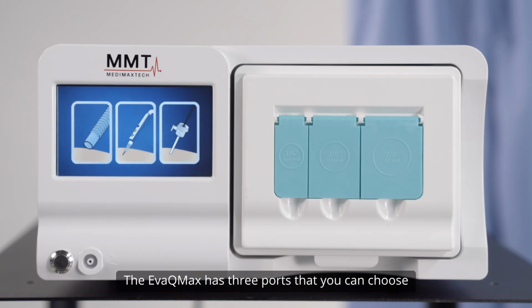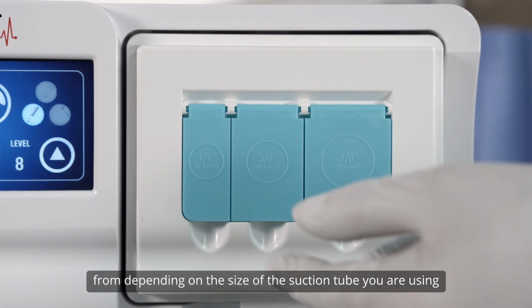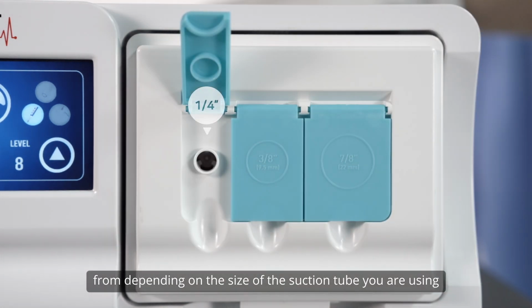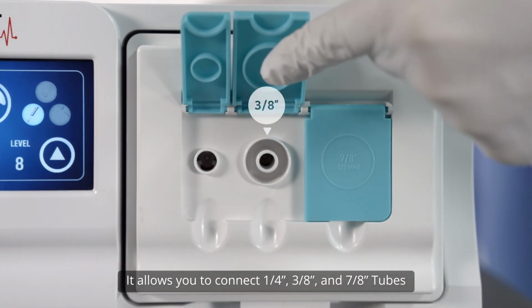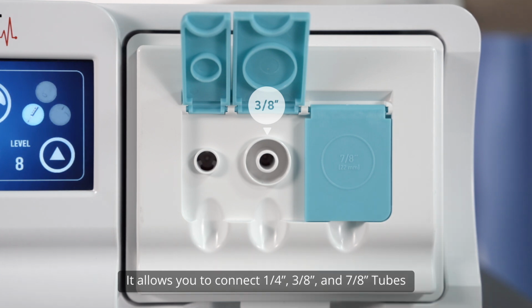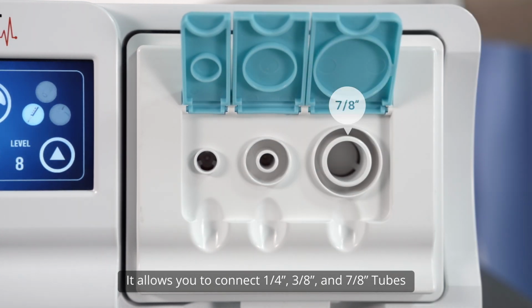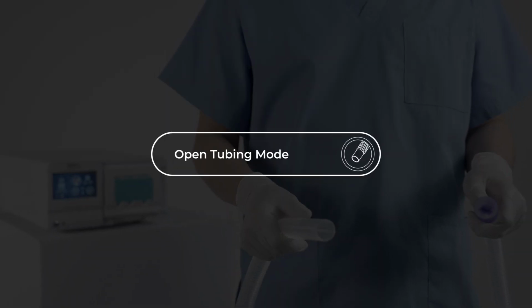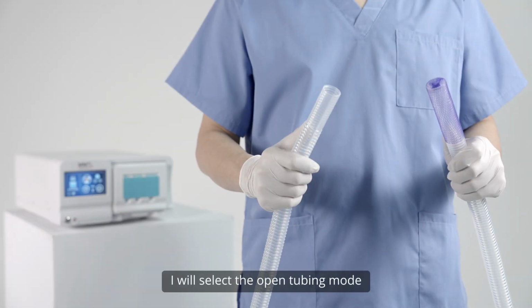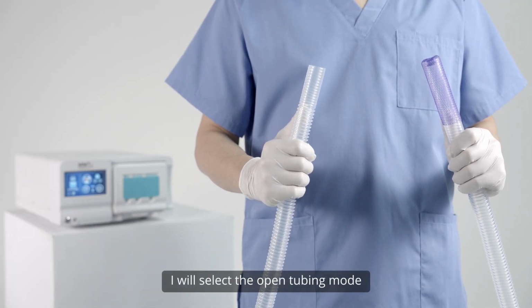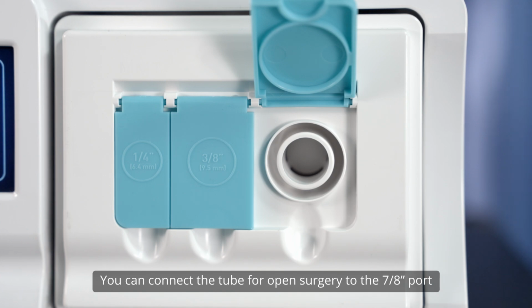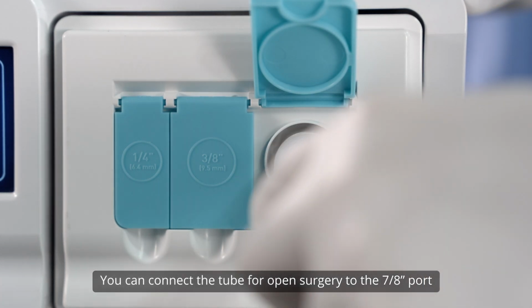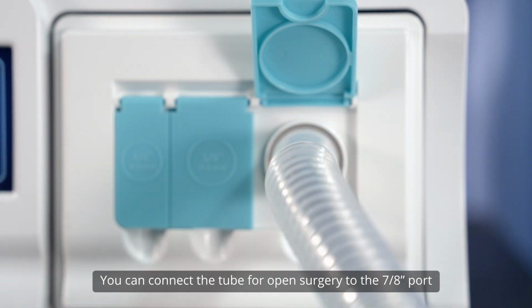The EvaQMax has 3 ports that you can choose from, depending on the size of the suction tube you are using. It allows you to connect 1/4 inch, 3/8 inches, and 7/8 inches tubes. I will select the open tubing mode. You can connect the tube for open surgery to the 7/8 inches port.